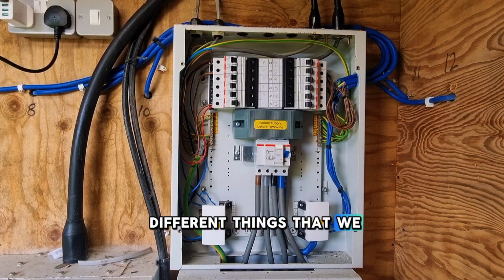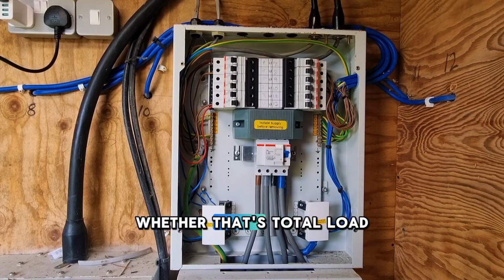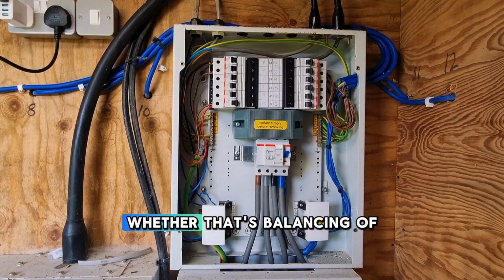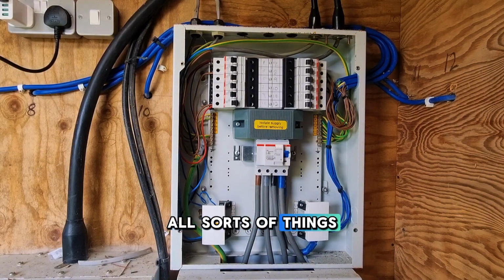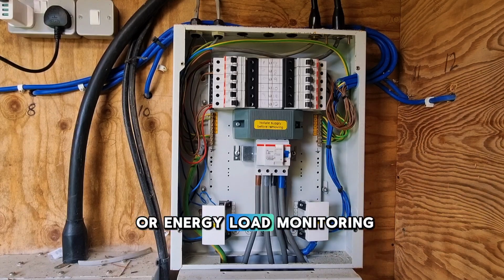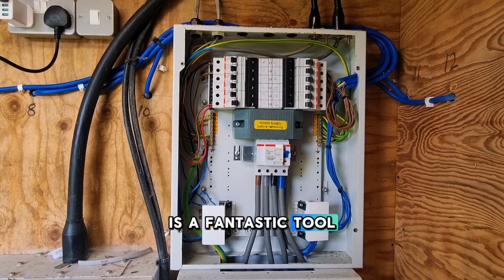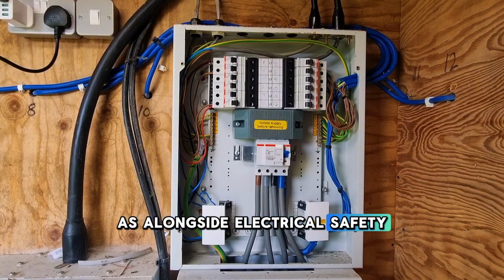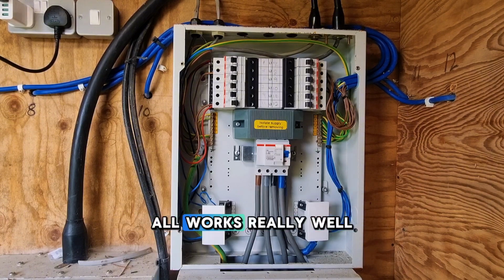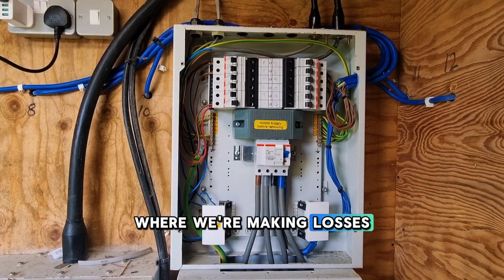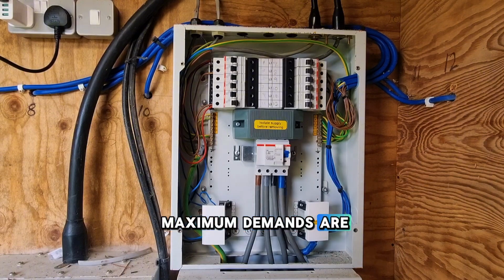There's lots of things we need to understand about power profile, whether that's power factor, total load, balancing of phases, and all sorts of other information. This power logging service, or energy load monitoring as we call it, is a fantastic tool and works really well alongside electrical safety inspections. The electrical condition reports work really well with thermal imaging too, helping us understand what's happening with the power in our premises, where we're making losses, and where our maximum demands are, making sure the installation is designed for that.